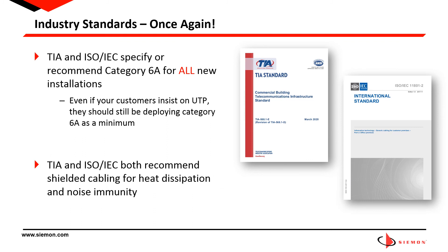So let's take a quick glance at what industry standards recommend. TIA and ISO-IEC recommend Category 6A for all new installations including healthcare, data centers, commercial buildings, and educational facilities in preparation for 10-gigabit-per-second application support. At this point, nobody should be deploying Category 5E or Category 6 for new installations. TIA and ISO-IEC also recommend shielded cabling for heat dissipation and noise immunity. So remind your customers who are running higher power PoE or are planning to, and any customers dealing with noisy environments, that this is the ideal medium.